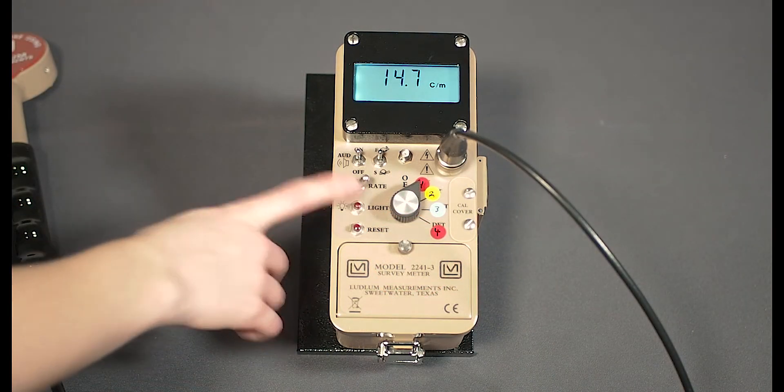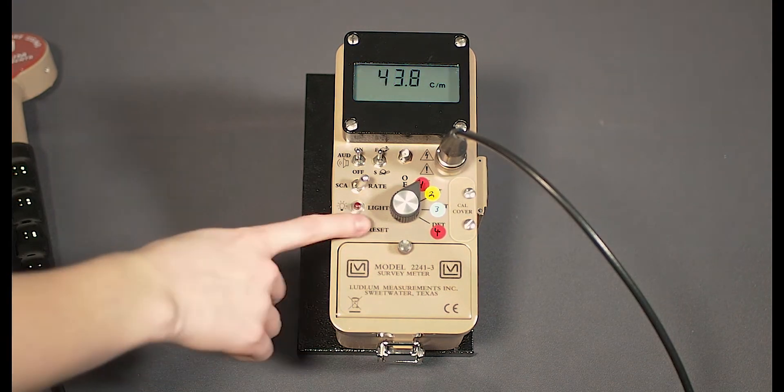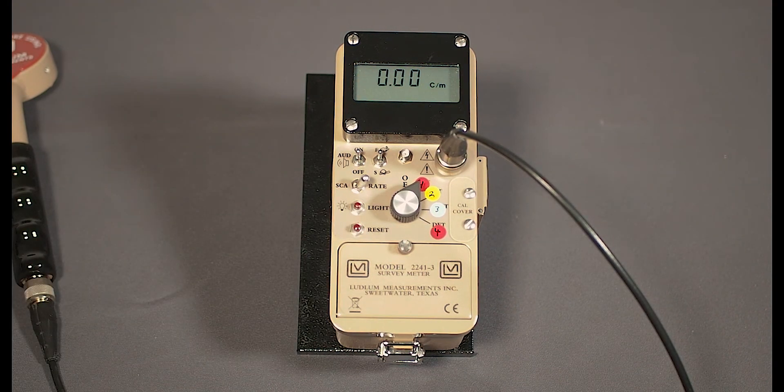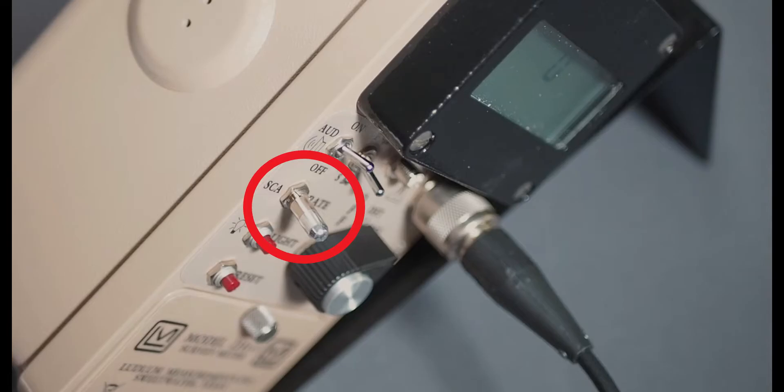The light button will illuminate the meter display for a short period of time. A reset button drives the display back to zero. There is also a protected toggle switch to change from rate mode to scaler mode and vice versa. This switch has to be pulled up before it can be toggled.